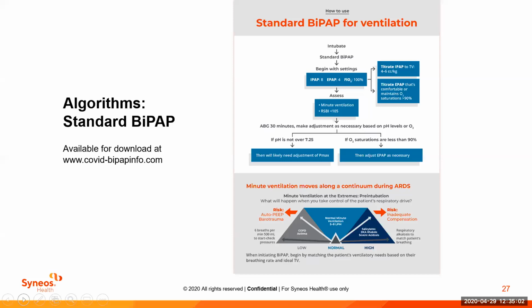So here, an IPAP, or that inspiratory positive airway pressure of 8, and EPAP of 4. For me, that's comfort. I've witnessed, unfortunately, some patients having IPAPs and EPAPs set early too high, in which case patients aren't comfortable or they're asynchronous with the device. And so using lower pressures and titrating, again, the IPAP to a level of tidal volume that's appropriate. And again, 4 to 6 milliliters per kilogram is what we suggest is appropriate. Because I think in that titration, you're going to hopefully find the work of breathing comes down, the minute ventilation stabilizes, and then you can assess your patient. I think the caveat to both of these algorithms is you're going to want early arterial blood gases to make those adjustments. I've made the suggestion of 30 minutes simply because we don't want folks to not show signs of stability, or more importantly, that you haven't had an opportunity to go back to the bedside to improve the condition of the patient. But again, Jamie, if you have any other pearls you'd like to share, I'd be happy to hear them.